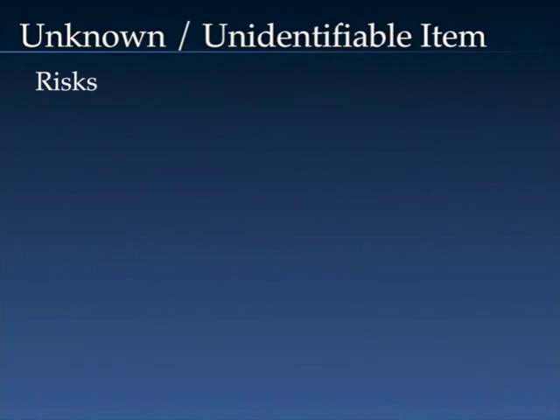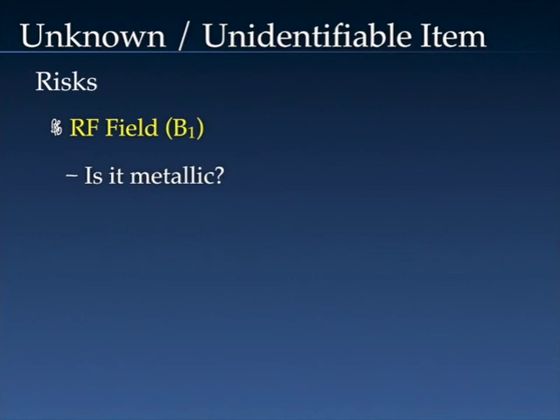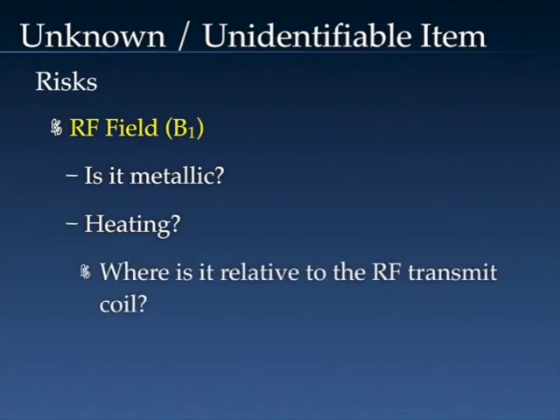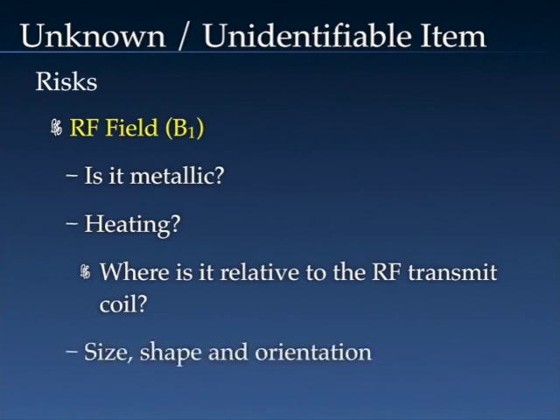There is also exposure to the B1 or RF field. As with any other magnetic field considerations, is it metallic? Because if it is, then it is conductive — and that's probably a given even if it's not ferrous. Would heating be of concern? That's going to depend on its location within the volume of the RF transmit coil, as well as its size, shape, and orientation. SMRT members have access to additional information on the SMRT website, including other videos and self-study materials, so if you have more detailed questions, please refer to that material.